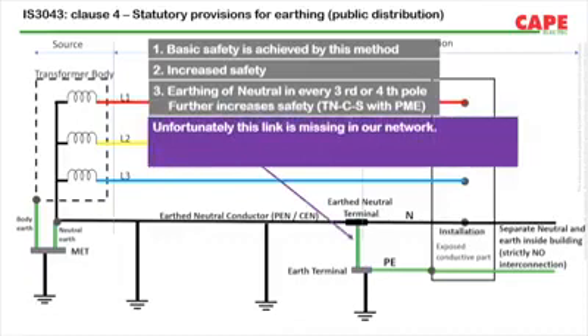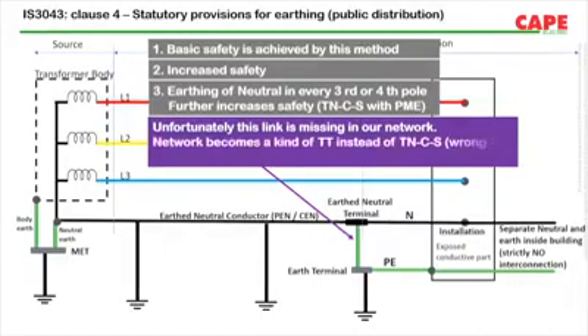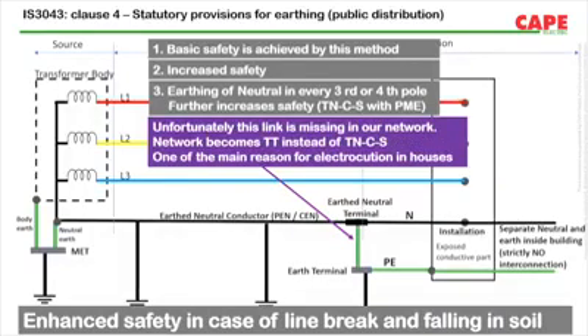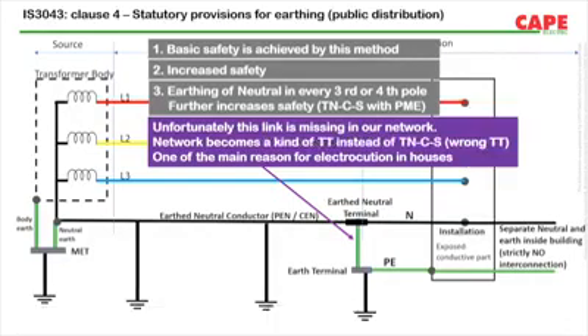Remember, neutral and PE conductor inside the building shall be strictly separate. Unfortunately, this basic safety measure is missing in our network. The link which is supposed to connect between the earth terminal and the neutral terminal is missing. As a result, the network becomes a kind of a TT but not a real TT. The low impedance fault return path is missing. As a result, the protective device is not able to disconnect the fault, which leads to an accident.